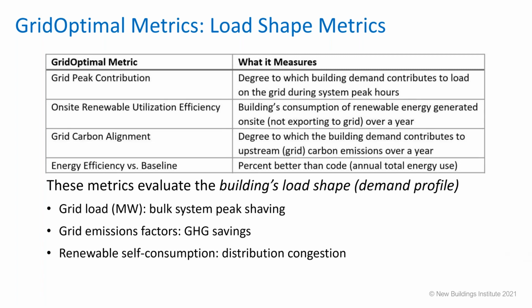Some of the Grid Optimal metrics have to do with the building's load shape, also known as demand profile, and how that compares with things on the other side of the meter—like system peaks in the utility grid. The grid peak contribution metric measures how peaky the building is during peak hours on the grid. Or it could be about carbon: how peaky is the building when the grid is relatively high or low carbon? How well aligned is the building's usage to the variability of grid carbon? Some charts Rushil showed earlier demonstrate how you can use this in a design context to think about building carbon emissions impacts.